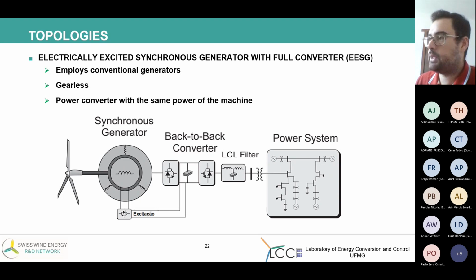Now we see the use of synchronous generators. Before, we had the use of induction generators, now the use of synchronous generators. Electrically excited synchronous generators with full converter. When we say full converter, that means that all the power, all the energy, passes through the converter. The generator employs a conventional generator, similar to the hydro generators, with the feed of current to the rotor. It can be gearless, and normally a gearless technology is used, with no gearbox. And so this is an advantage.